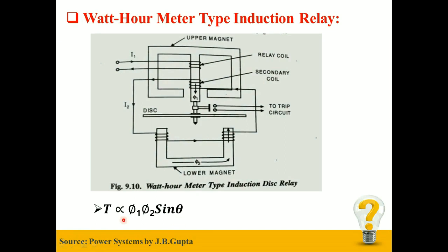During normal condition, this deflecting torque is not sufficient enough to rotate the disc. But during abnormal condition, as current heavily increases, the deflecting torque also increases, which rotates the disc and closes the contact, which sends a trip signal to the circuit breaker and protects the system.